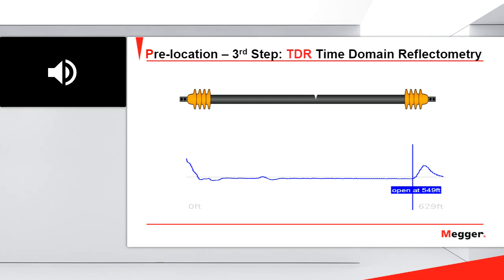And the question is, why did nothing happen at the fault? Very simple. This is a 15 kV cable, and it has a fault, and the fault is a pinhole. This cable is faulted, but maybe to flash over this fault, I need, let's say, 6 kV. So 6 kV means 6,000 volts. When I send a low voltage pulse, let's say 15 volts, 50 volts, when the low voltage arrives at the fault, nothing happens. Why? Because 50 volts does not have enough energy to flash over a fault of 6,000 volts. For that reason, we don't see anything over here.